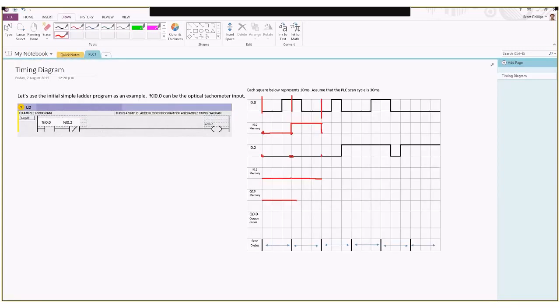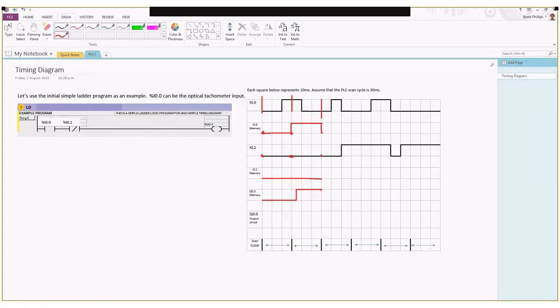That's showing the time that it takes for our PLC to store the values from the inputs into the memory, and then once it gets into solving the logic program, it's going to decide it needs to turn on this Q0 memory. That's going to be up until the end of that scan cycle. Our physical output for this output Q0 always happens at the end of the scan cycle, so looking at this point around here.